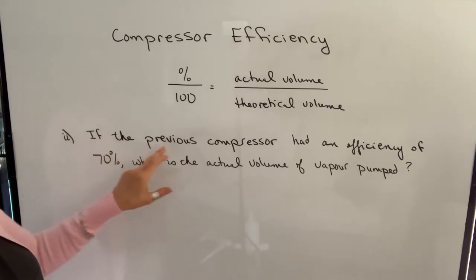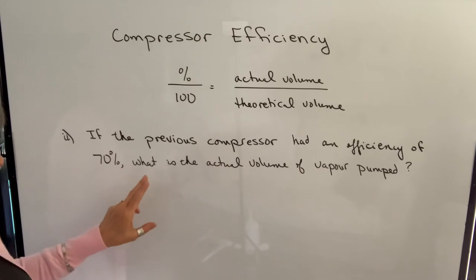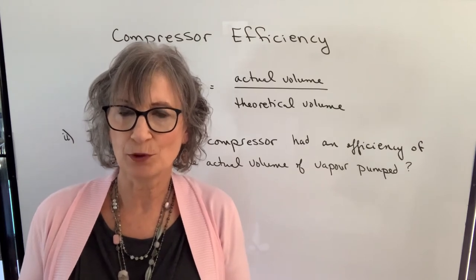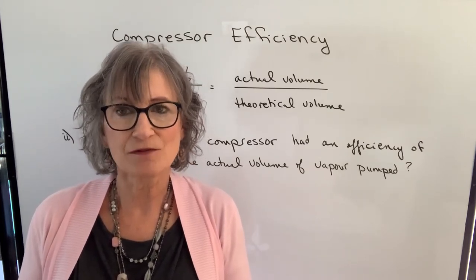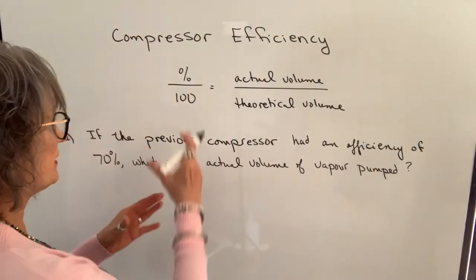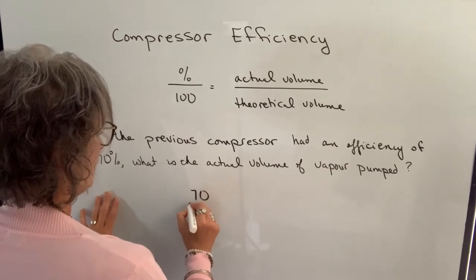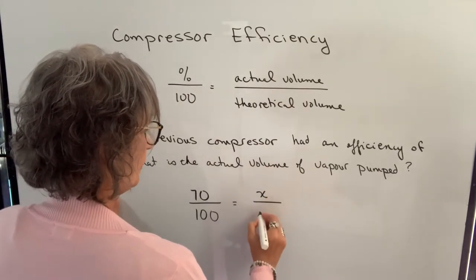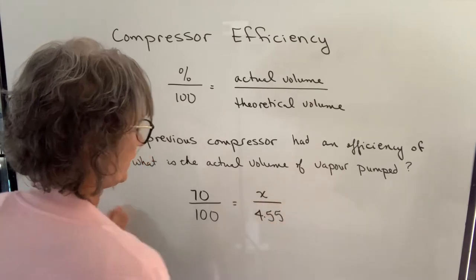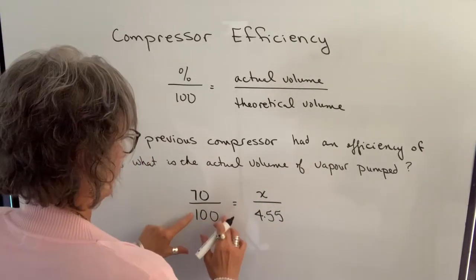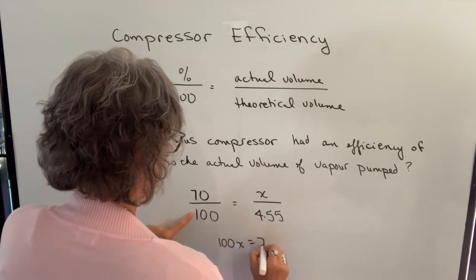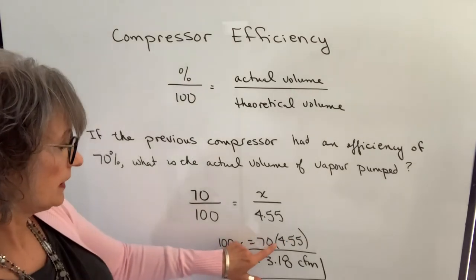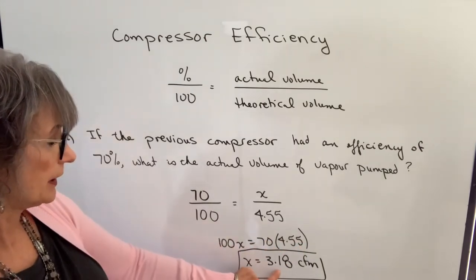First example: if the previous compressor had an efficiency of 70%, what is the actual volume of vapor pumped? We knew that the theoretical displacement was 4.55 cubic feet per minute, but let's find out if it's operating at 70% efficiency, what the actual displacement will be. So we're going to set it up using this as our guideline. 70 is the percent, it goes over 100. The actual volume is what we're trying to find. The theoretical volume was 4.55 cubic feet. And then we can cross multiply to solve this equation. So 100 times X will equal 70 times 4.55. In order to solve for X, we divide by 100.